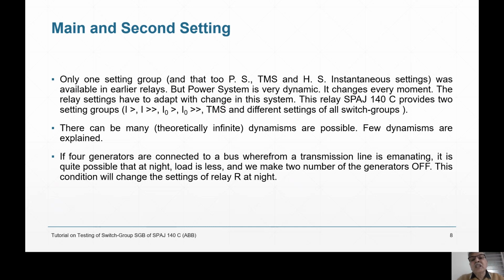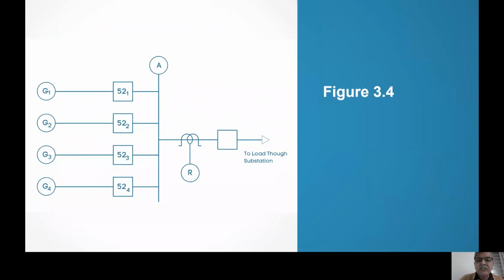Because your power system is not static, it is highly dynamic. I can give you 100 examples of dynamism of the power system, but time will not permit. So I cannot give 100 examples, but I will give you a few examples where you need two different settings, two plug settings, two time multiplier settings. Such facilities are required because your power system is not static. It's not that once you have started feeding power, that's all and no change will be there. It's not like that. There will be many changes every moment, every time. You see, in the morning the power system is different. In the afternoon, it is different. So how is the power system dynamism there?